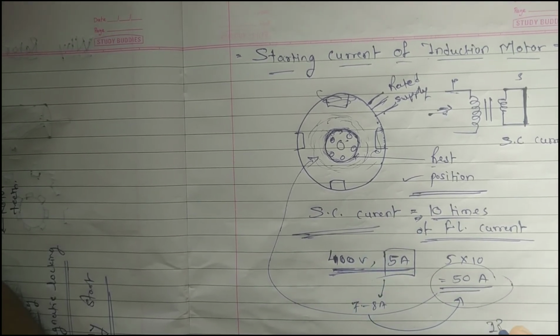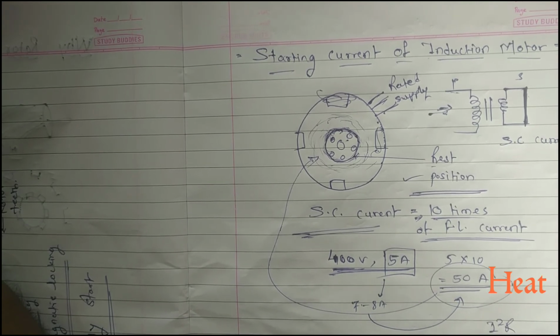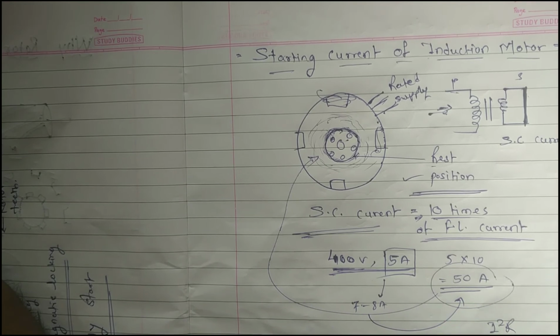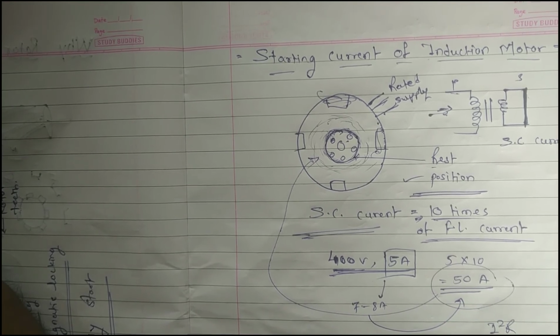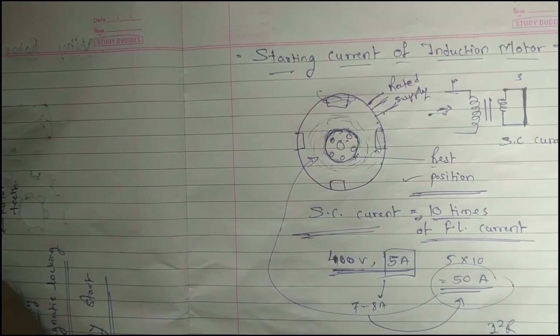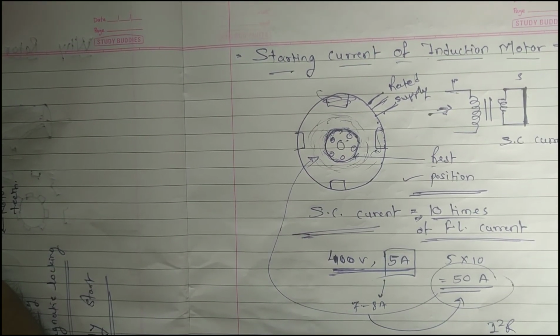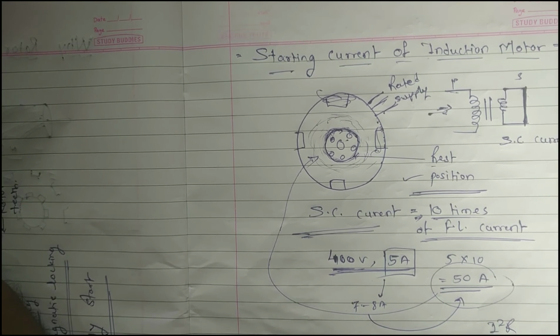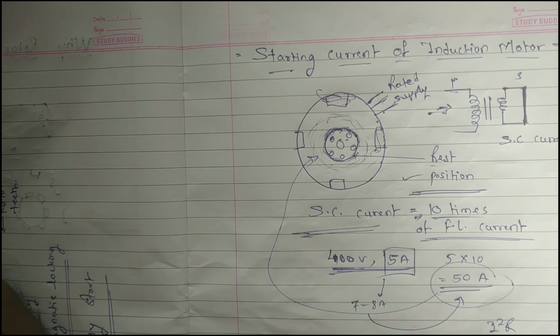It means there will be I square R losses, nothing but heat. Your winding will become red hot and it will damage your rotor circuit. So this should not happen. This is the starting current of your induction motor. That's why there is a necessity to use a starter to start the motor.